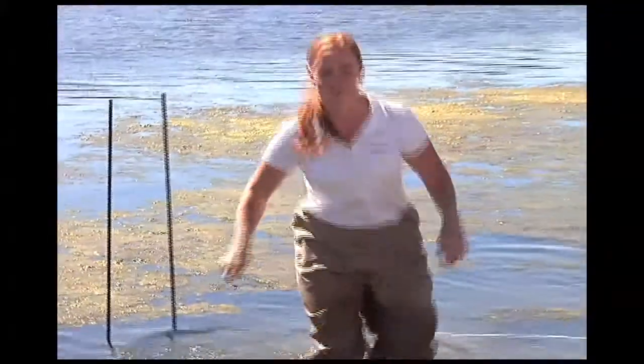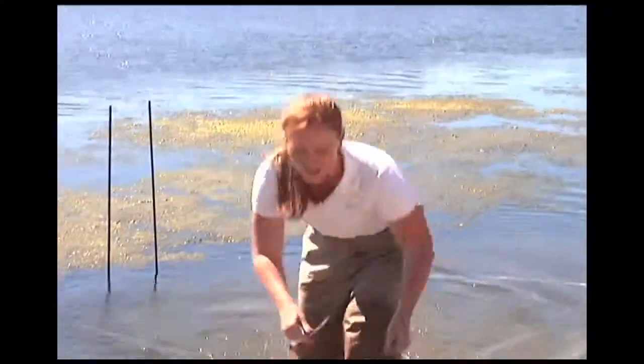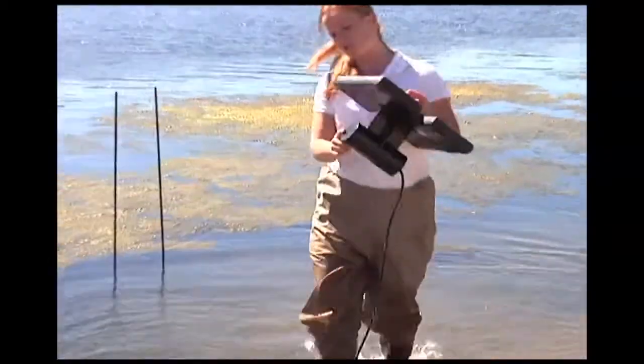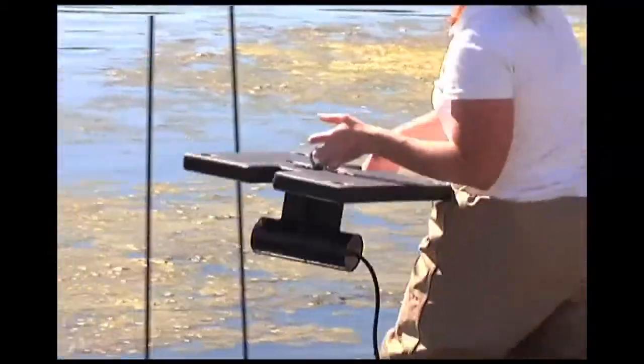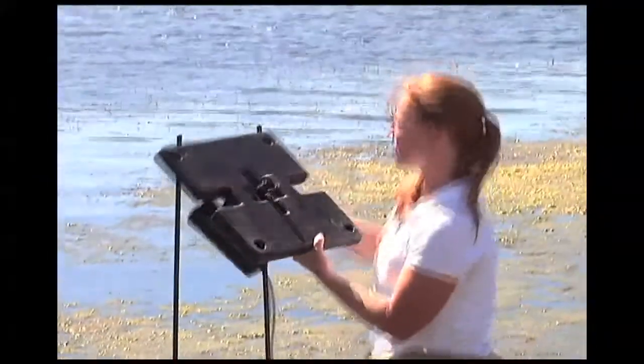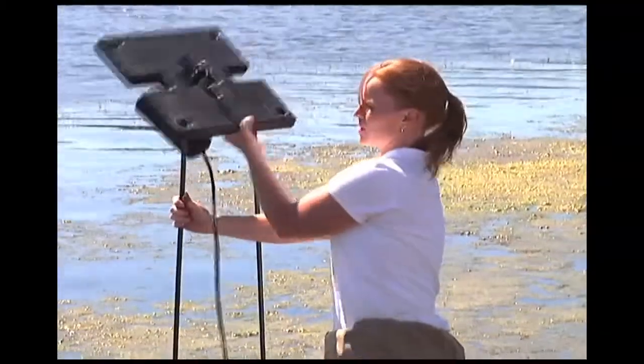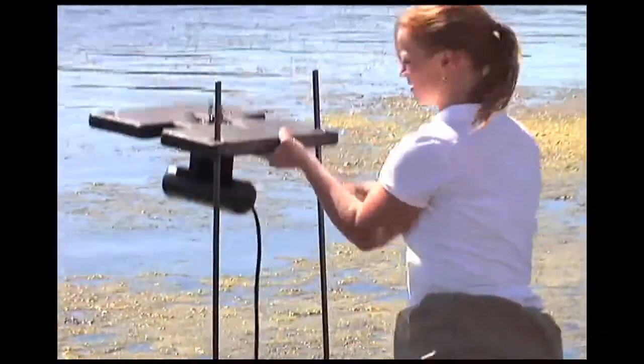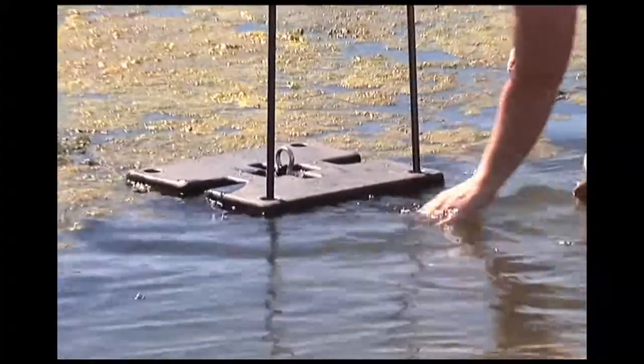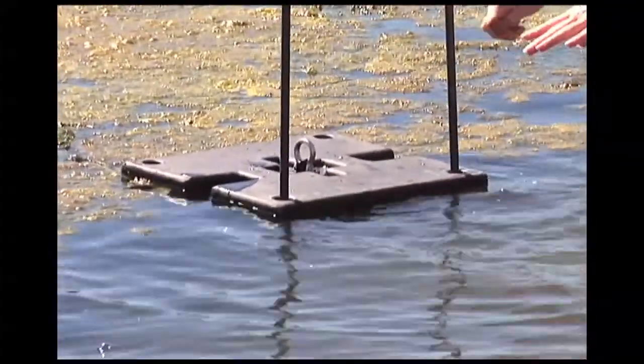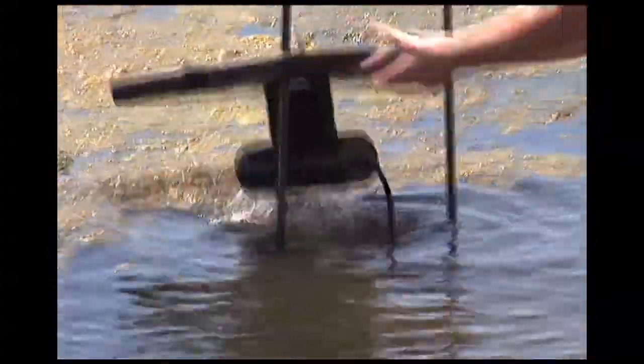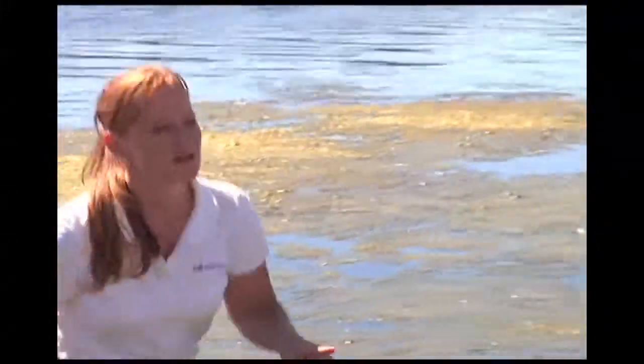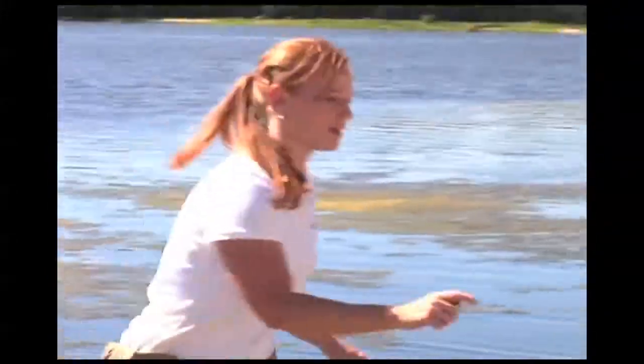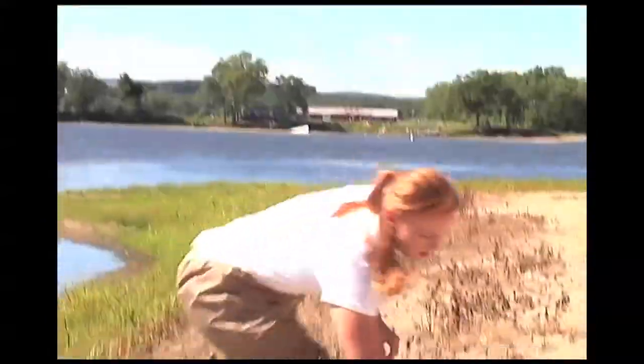Next, we're going to take our unit and place it on the poles of the sled mount. You want to make sure that the transducer head or the flat part is facing out. We're going to put the poles through the back holes of the float. You'll notice that we installed this at low water levels, but when the water rises, the float can go up and down on the poles. The last part is taking the rope and securing it to the stake on shore.